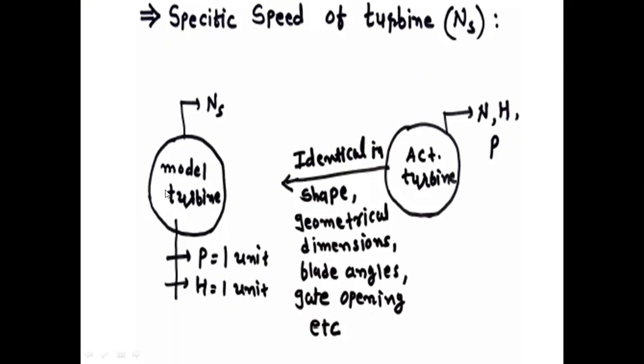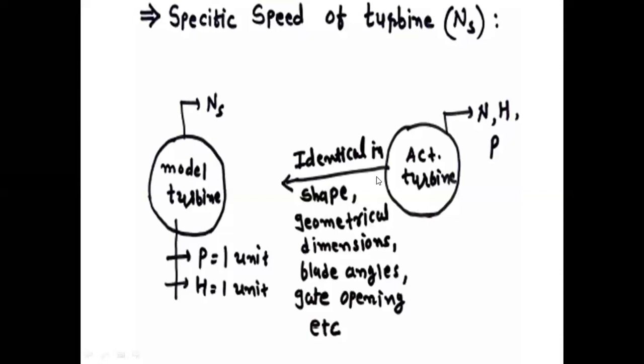Now, design one model turbine which is operated under a unit head — that means H is equal to one meter — and produces one unit power, that means P is equal to one kilowatt. This design model turbine must be identical with the actual turbine in geometrical dimensions, meaning blade angle, gate opening, etc. The speed of that model turbine is considered as the specific speed of turbine.